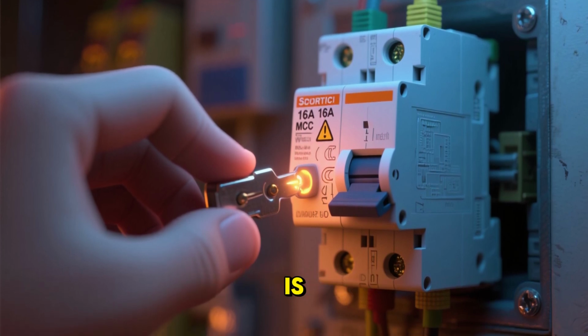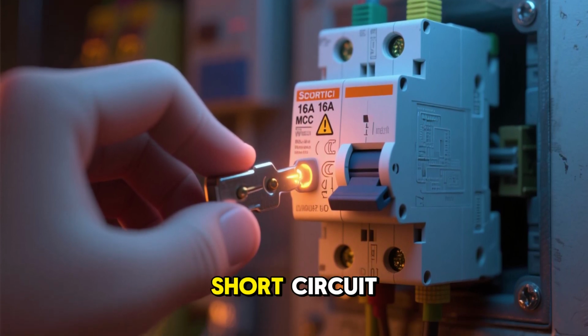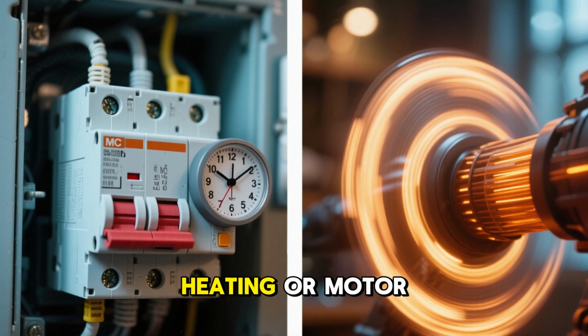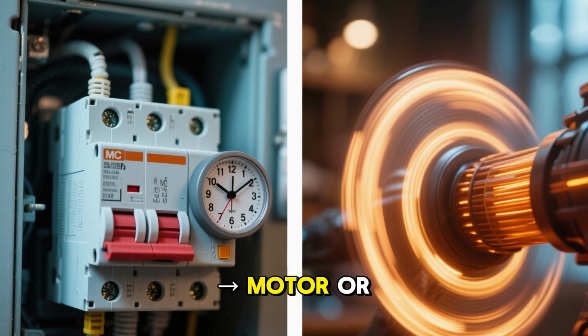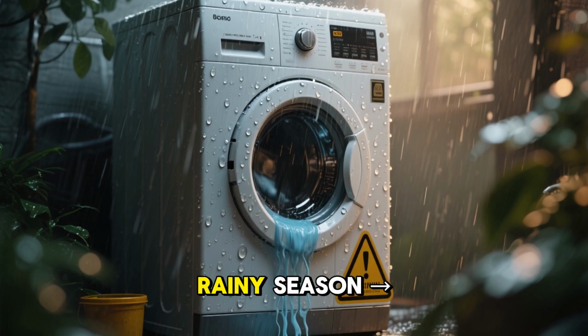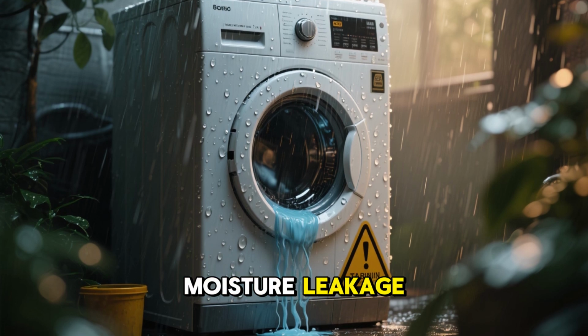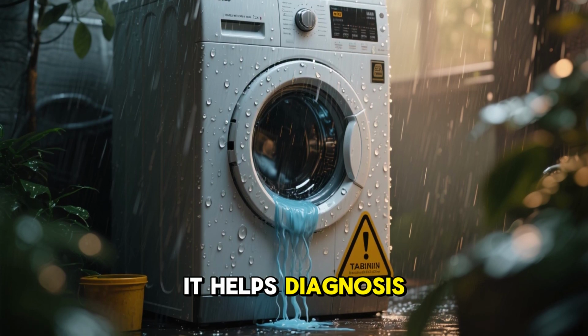This tells you where the fault is. Trips immediately means short circuit. Trips after a few minutes means heating or motor. Trips during spin means motor or wiring. Trips only in rainy season means moisture leakage. Observe the timing, it helps diagnosis a lot.